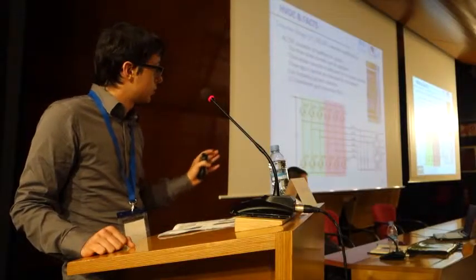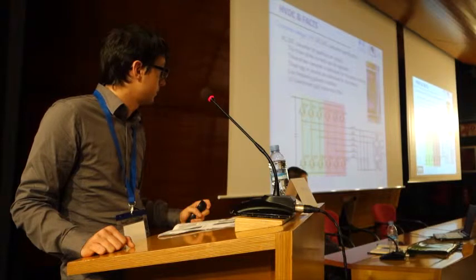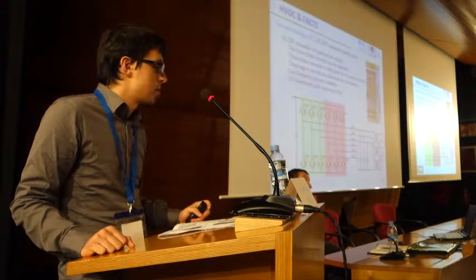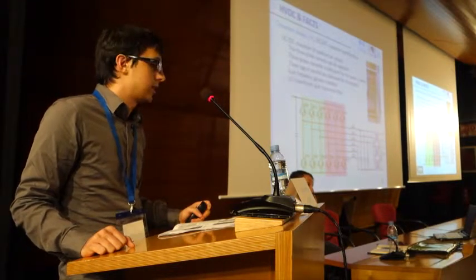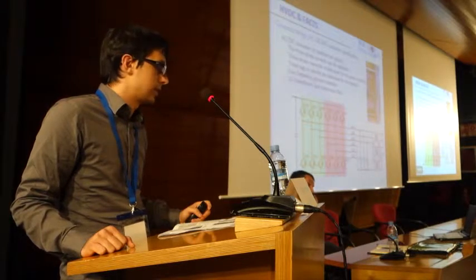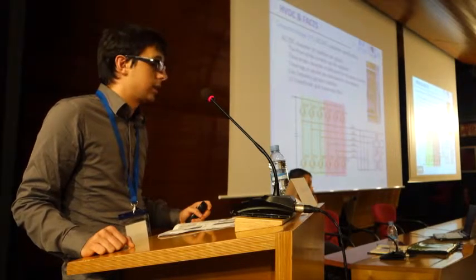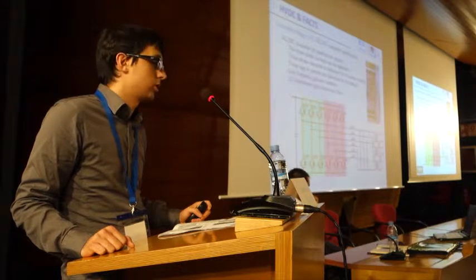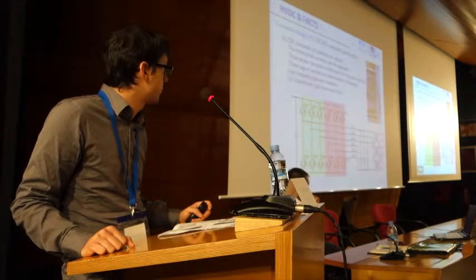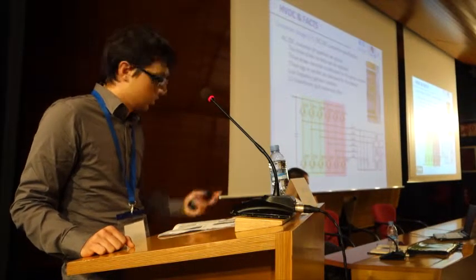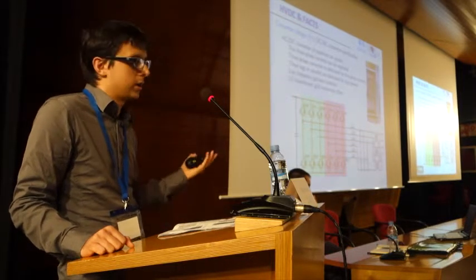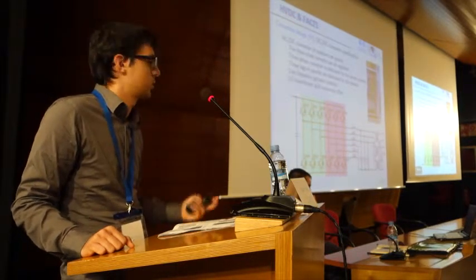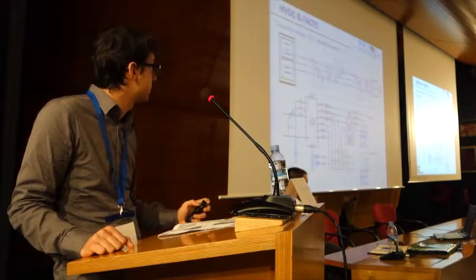And we have decided to use 3 single-phase galvanic low-frequency transformers because, if we have a system that can control the direct, inverse, and homopolar components, and we need galvanic isolation, we need that this galvanic isolation also gives the system a homopolar magnetic path to operate. So in this case, one of the ways to do that is using 3 independent single-phase transformers.